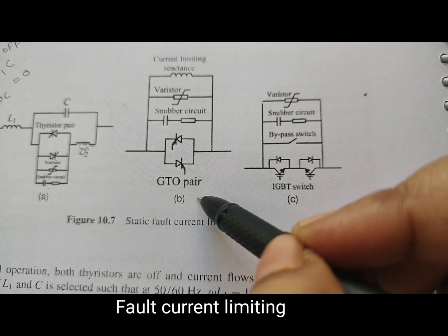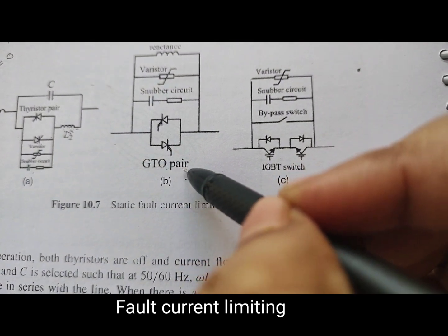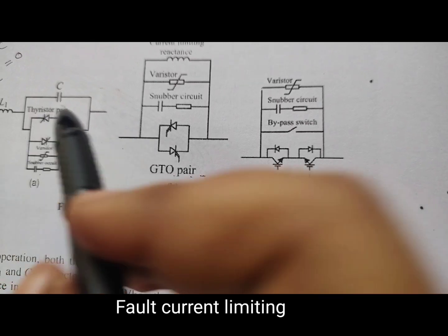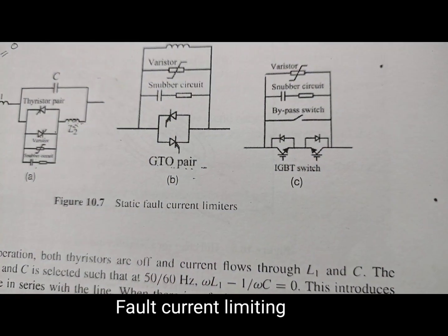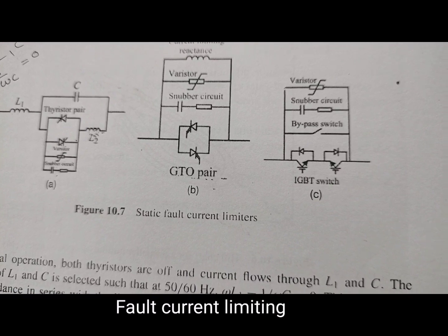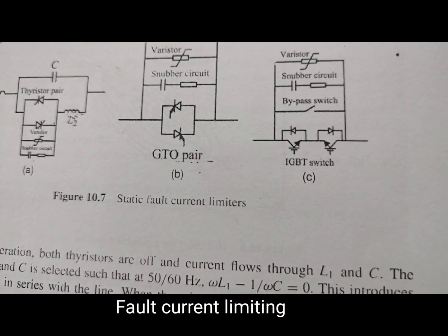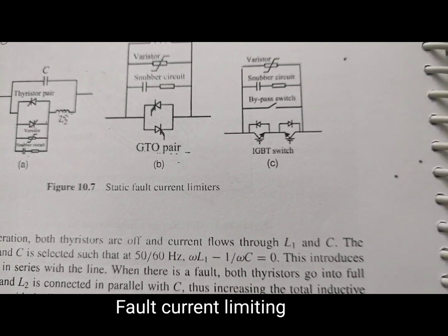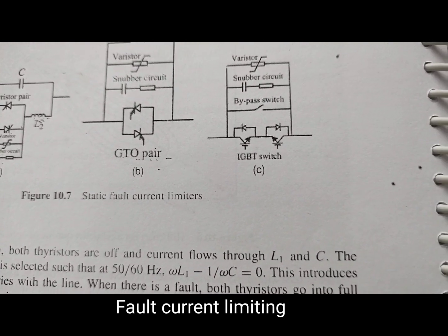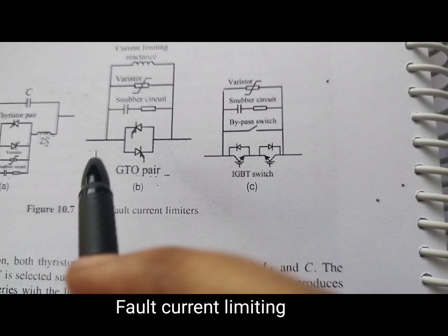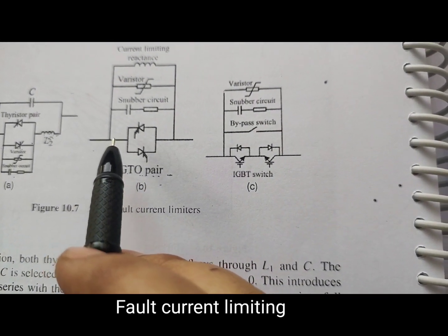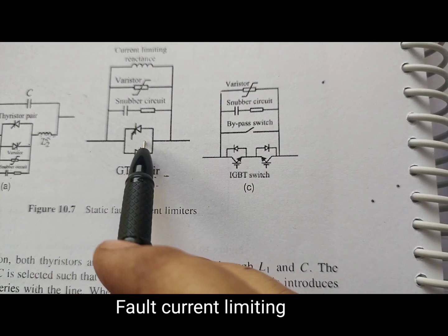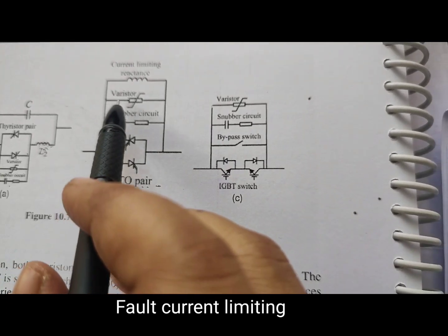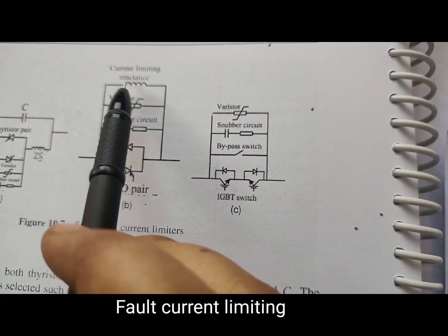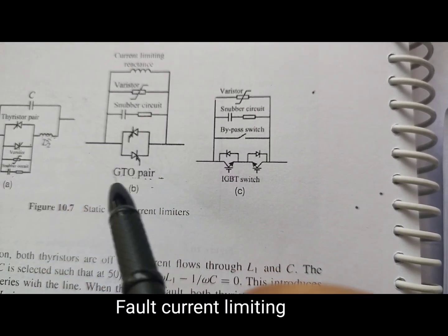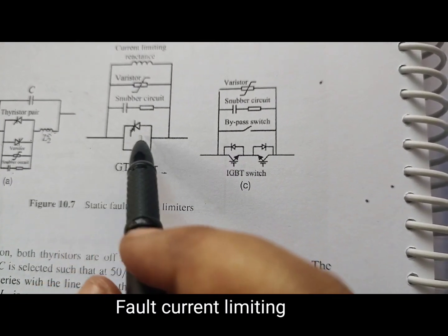Next, in figure 2, that is the GTO pair. Here they have used GTO, gate turn off thyristors, placed in series with the line. When a fault is detected, the normally conducting GTO is switched off and the current is diverted to the parallel reactance. During the normal condition it will flow like this.